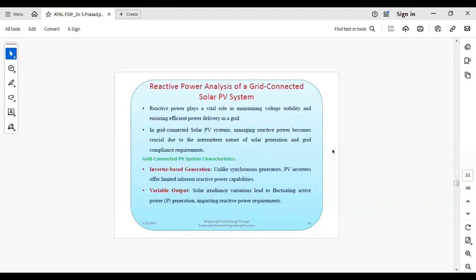Reactive power analysis of a grid connected solar PV plant. When a PV plant is connected to the grid, you have to conduct reactive power analysis also. To avoid voltage instability at the point of interconnection, you must have a reactive power compensating device at the PV station, so that you maintain the power factor according to CEA regulations. According to CEA regulations, you have to maintain the two extreme situations, 0.95 lagging to 0.95 leading. These are the two worst case scenarios, so you have to perform the reactive power analysis for these two cases. You have to maintain 0.95 lagging to 0.95 leading power factor at the point of interconnection.